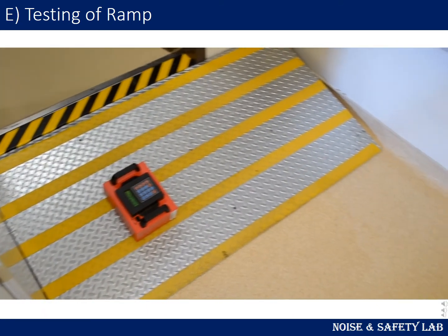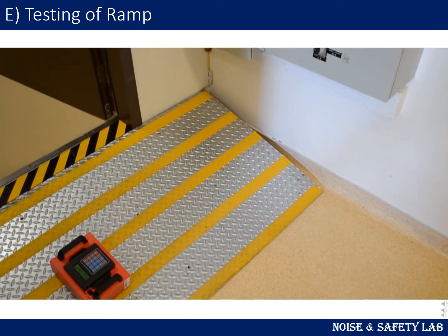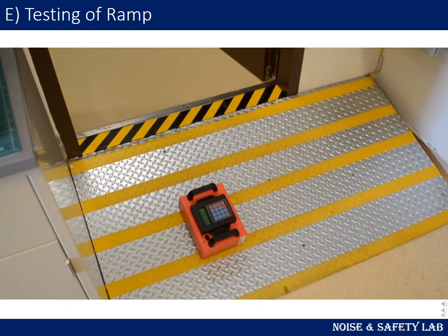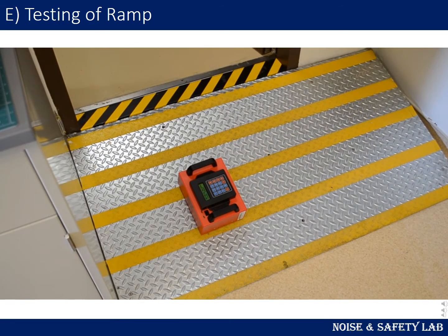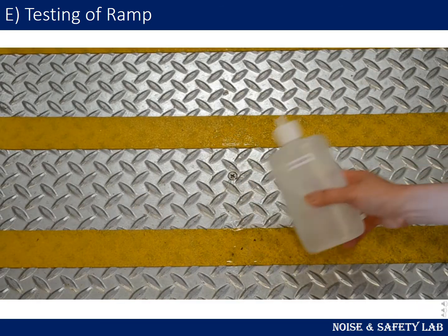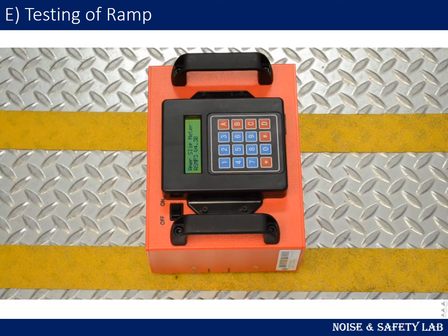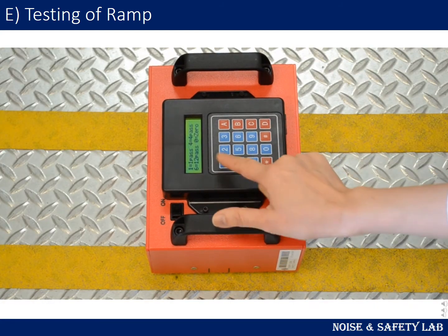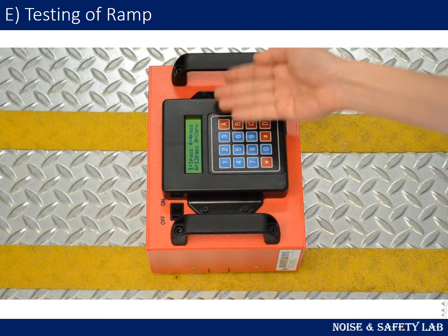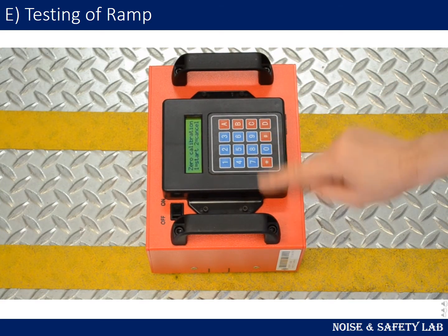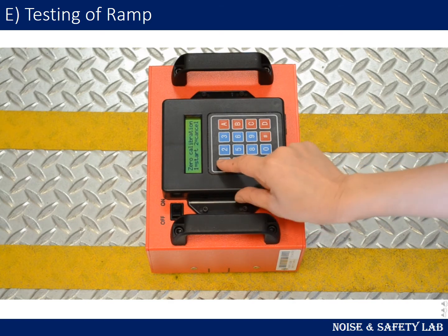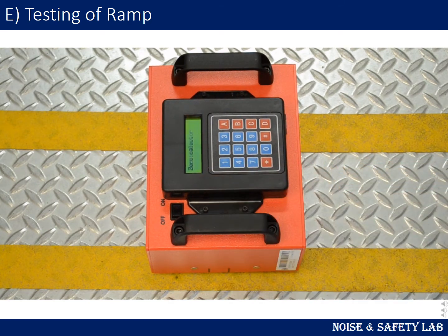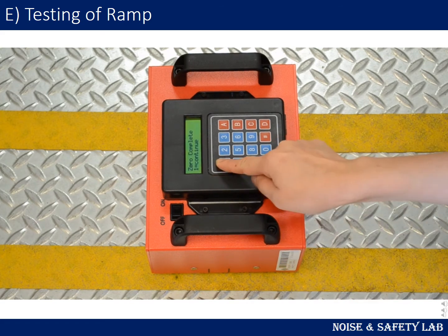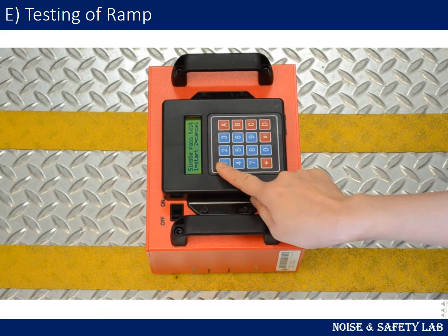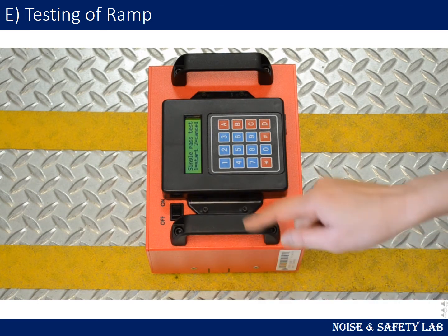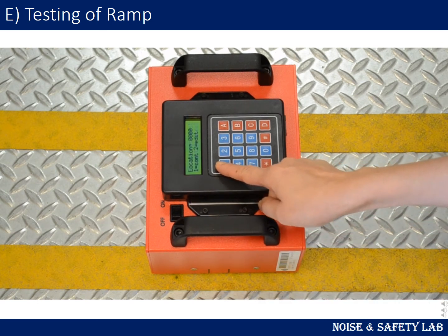For the investigation of a ramp's friction, we need to measure the DCoF values for up the slope, down the slope, and perpendicular to the slope. For the up-slope test, put the right handle of the meter at the uphill side. Repeat the zero calibration at this position. When zero calibration is completed, press 1 to select single pass test for going into your testing.